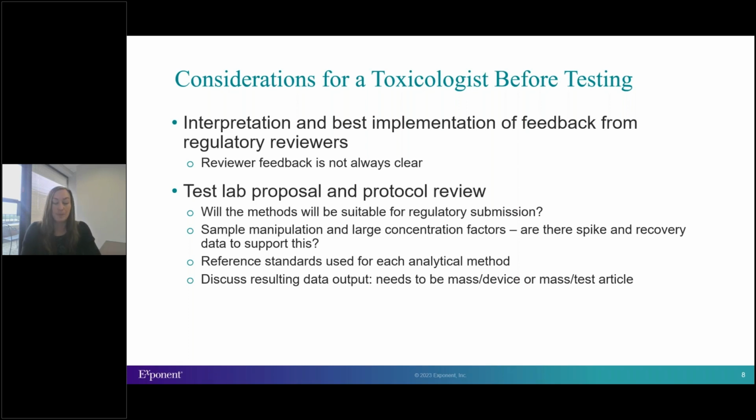So we pushed back on that. We provided a literature-based rationale for why a 37 degree Celsius extraction temperature would be appropriate and still worst case for an extraction scenario. That was considered acceptable by the reviewers, and I'm really glad that we asked about that so that we don't overdo it with our extractions.